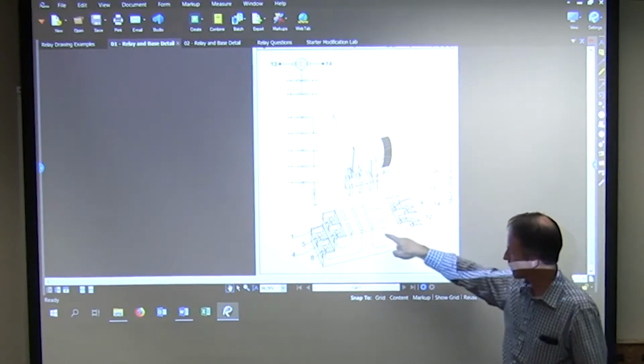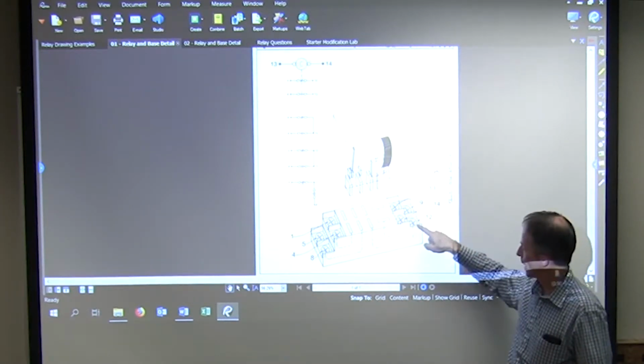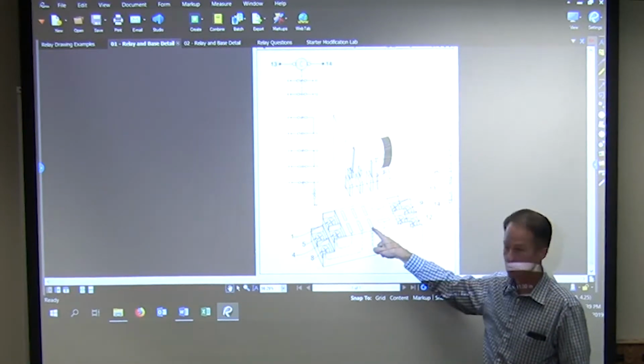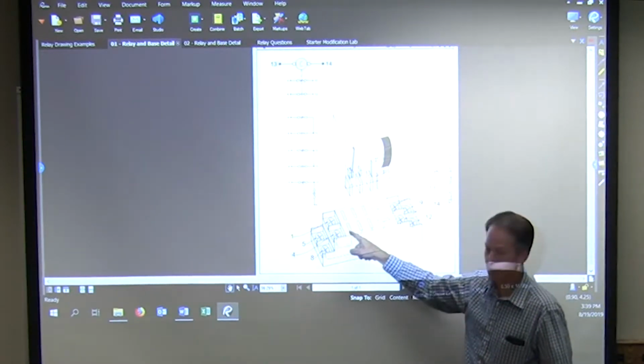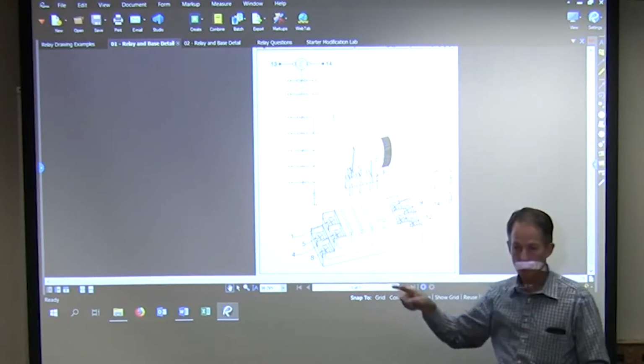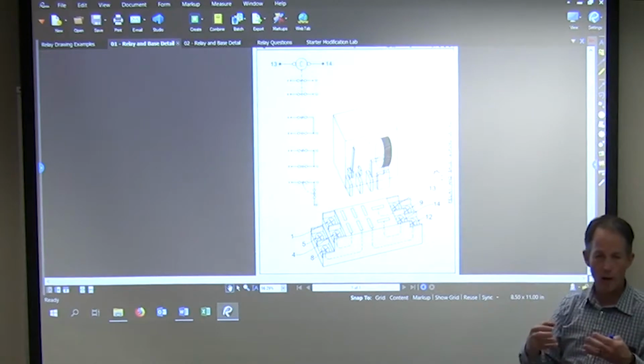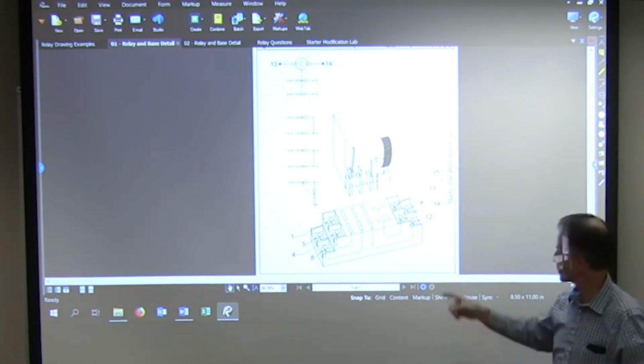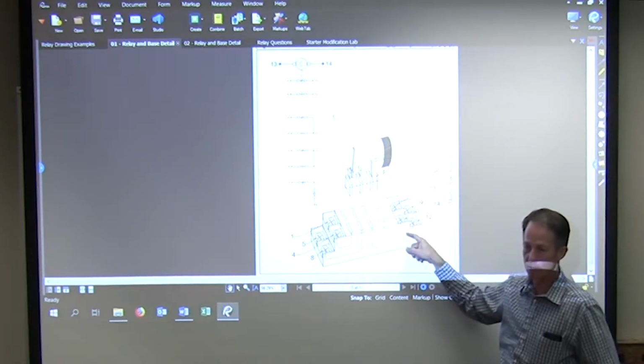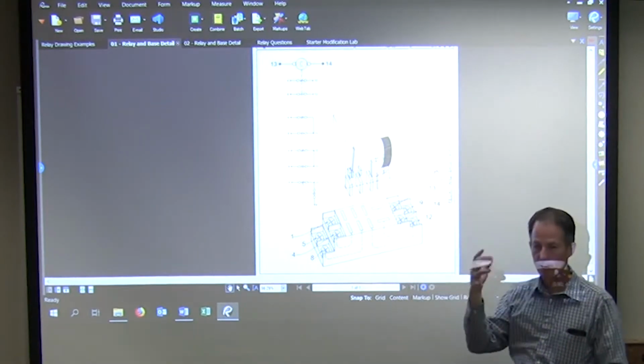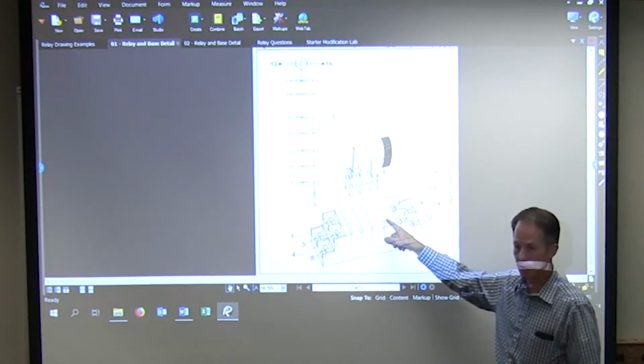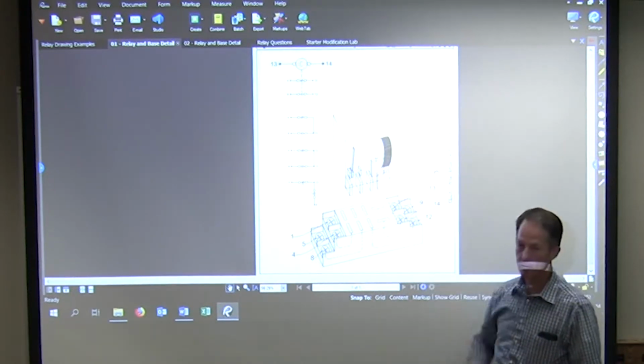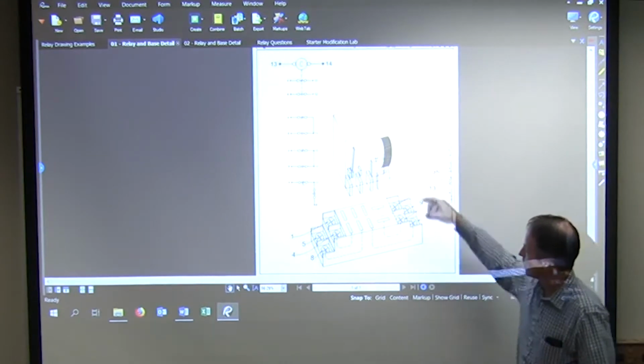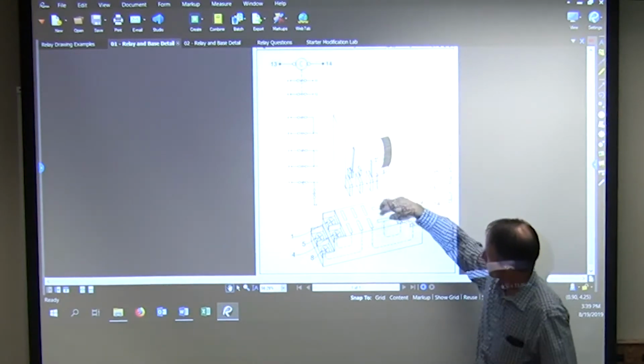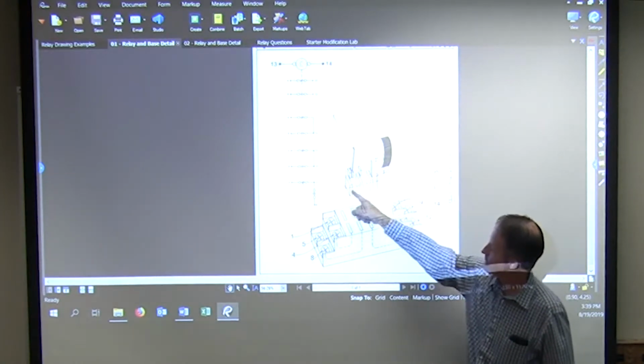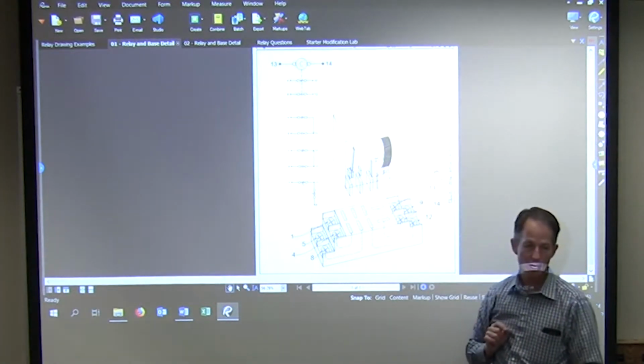Now, you'll notice internally how these are wired. The bottom screws kind of go out and come into the middle on both sides. The top screws come to the edge terminals. If you think about it, the manufacturer putting these together is not going to want to cross wires. So if you're ever not sure, just remember close ones go to the top, bottoms go to the middle. Okay. So we have our coil, our electromagnet, plug into these two. Then we have three other tabs for each set of contacts.